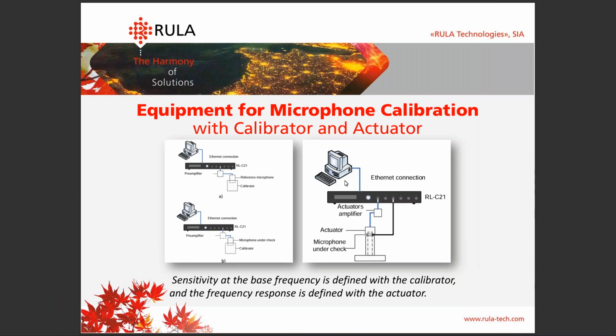Now to microphone calibration, and here you can see a more complex picture. And this is an ideal situation standard. In this situation, sensitivity at the base frequency is defined with a calibrator, and then the frequency response is defined with the actuator. So you're going to need a controller, a preamplifier, your reference microphone, your microphone under check, and a calibrator to measure sensitivity. Then you're going to need a controller, an actuator's amplifier, an actuator, and the microphone under check to measure the frequency response. So it's a slightly more complicated scheme, but we are ready to guide you through the connection and the necessary hardware to collect the complete system.